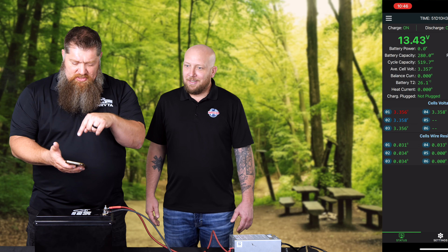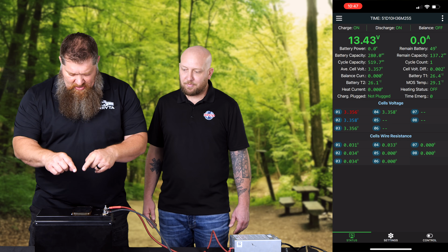So what we're going to do is conduct a test. We're going to plug it in, and on my BMS we'll be able to check the amperage. This is a WFCO 50 amp model, correct? So we should see roughly 50 amps when we first plug it in, as it's identifying - as long as my battery is sufficiently discharged, and we got it down to 49%. We're recording the screen grab on the BMS inside right now, and currently we're sitting at 0 amps because this is not on yet. So let's go ahead and plug it in.